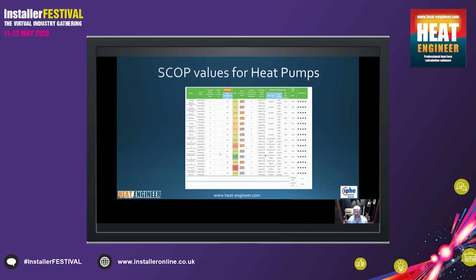Very, very important if you're MCS certified, or if you are doing heat pumps as a major installation process for underfloor heating. Again, with underfloor heating, depending on the size of your U value and the heat loss for that particular project, you've got your different floor types, like carpet, but it actually then gives you your pipe spacings, which is very, very important, because we know that many companies will go out and put in 100 millimeter pipe centers for pretty much every single project.